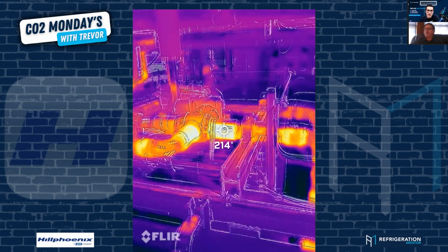Here's another beautiful shot of a 3-way valve, it looks like. Yeah, you can see the path of operation. It's coming down from the separator, up and turns left, and then comes out the bottom, the normal path of flow to the condenser. If it was to go straight, it would have been to bypass the gas cooler. Yeah. And like these are such great images.